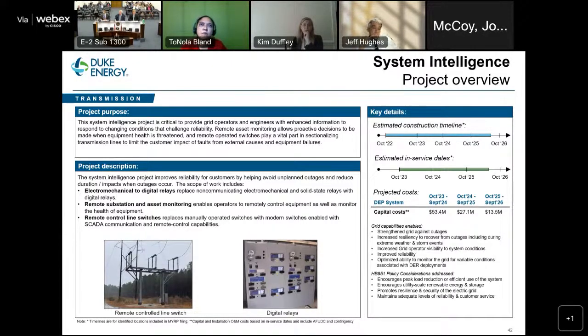Remote asset monitoring is the second item I'll mention, both remote asset monitoring and substation monitoring. Most folks are familiar with traditional SCADA, getting information from substations back to the control center and being able to control that equipment. Asset monitoring takes SCADA down to the level of a specific asset—in this case, transformers.